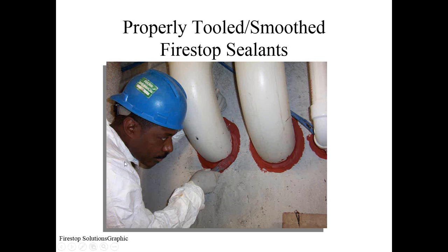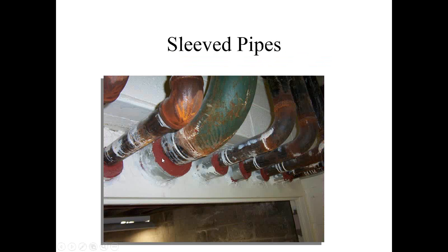Let's go to the next one. Take a look at this picture. Look at the sealant here, how smooth it is. The Firestop sealant has been adhered to the metal sleeve and adhered to the metal pipe.